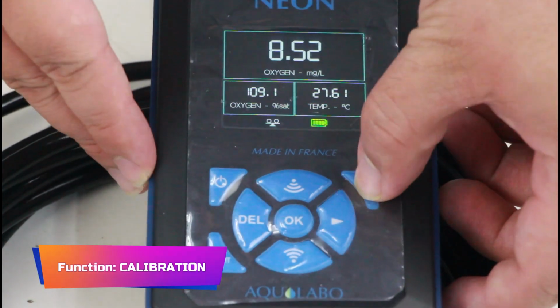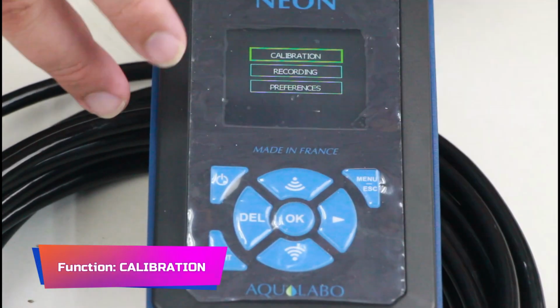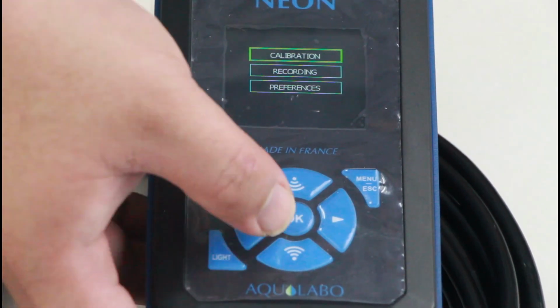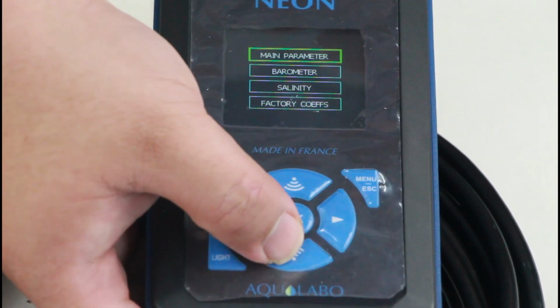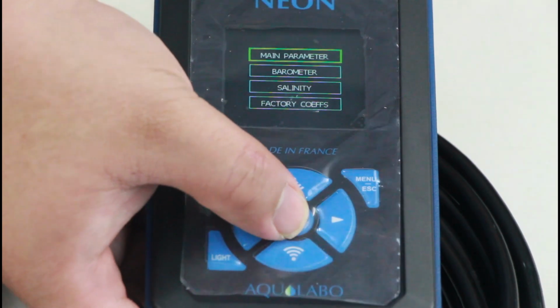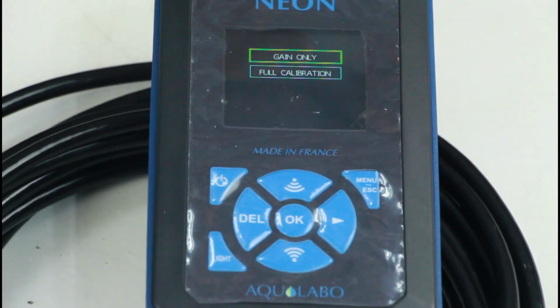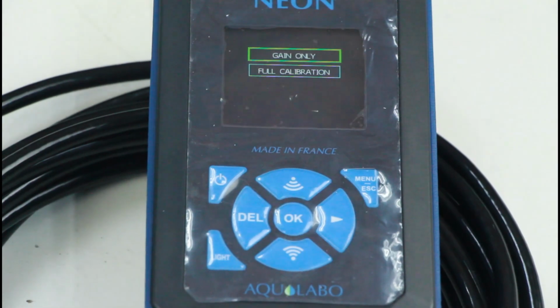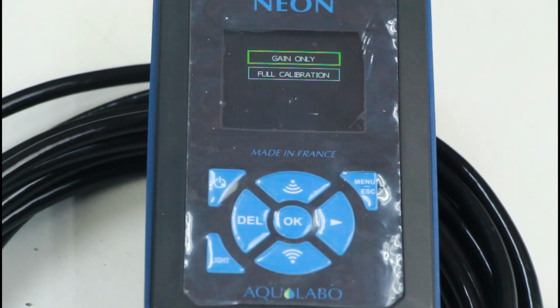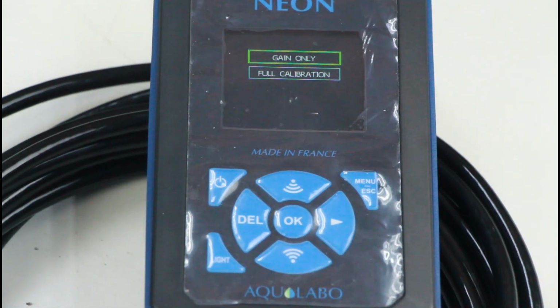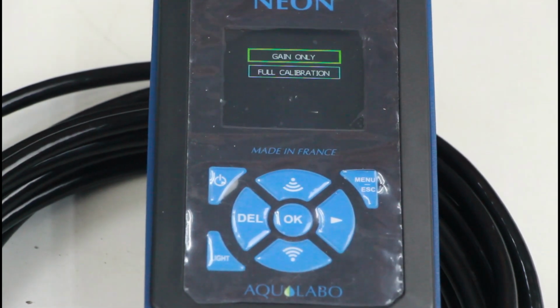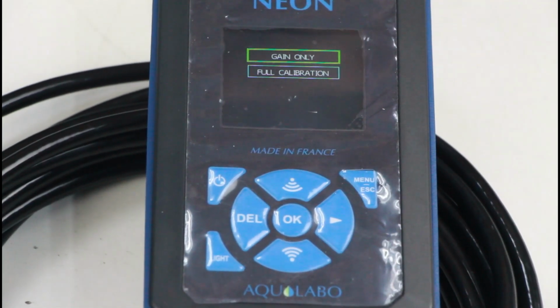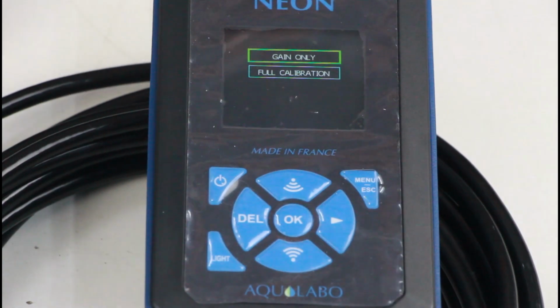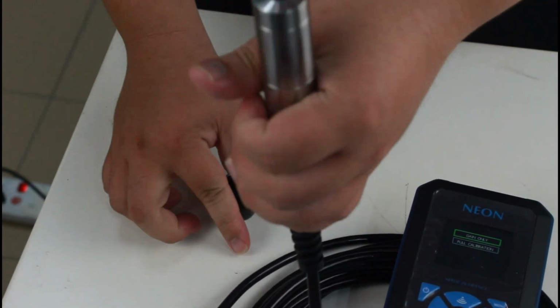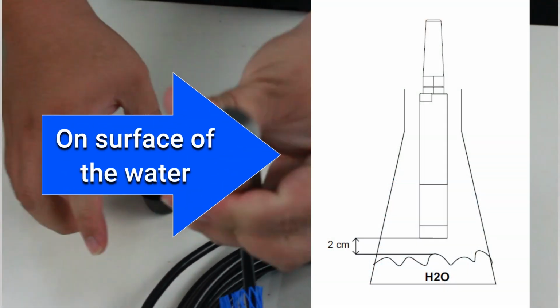Okay, as for the calibration part, we can press the menu here and access calibration. Inside this calibration, we go for the main parameter here, which is dissolved oxygen. We got 2 functions here. One is full calibration and the other is gain only. Normally, we recommend customers to do the gain only function. Gain only means that you need to place the probe onto the surface of the water.